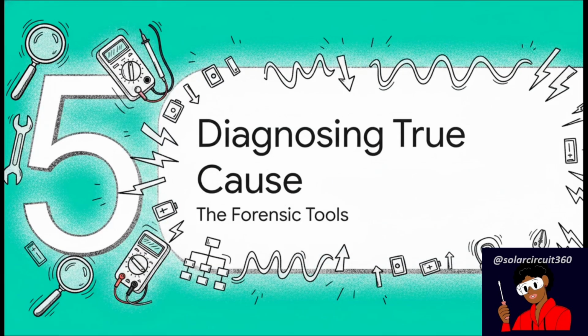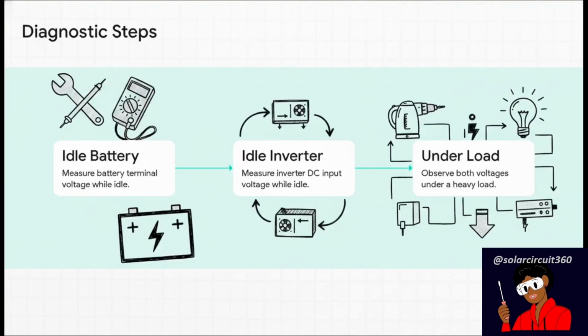Which brings us to Section 5, Diagnosing the True Cause, the forensic tools. Now that we know who the real suspects are, let's get you equipped to actually test your system like a pro. This sequential process is absolutely crucial, so put down the wrench and grab your multimeter. Step 1, check the voltage directly at the battery terminals while the system is totally idle. Step 2, check the voltage at the inverter's DC input terminals, also while idle. And step 3, this is the big one. Watch exactly what happens to those voltages the very second a heavy load kicks in.